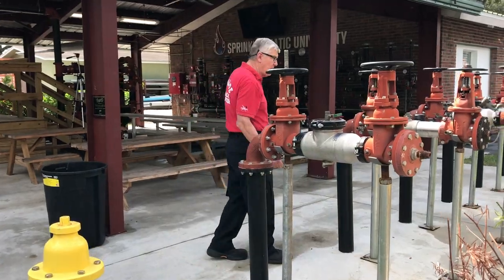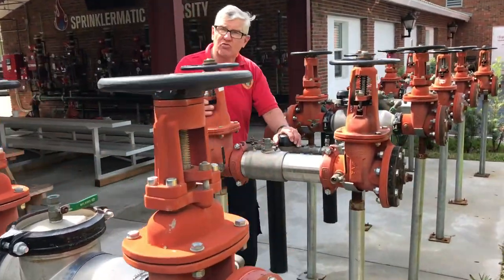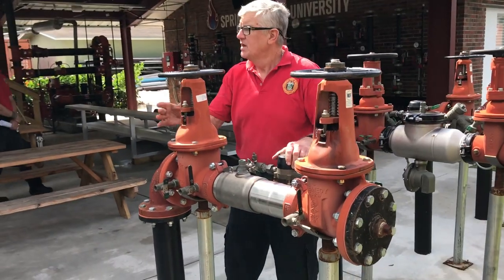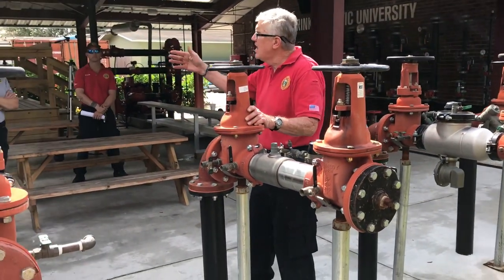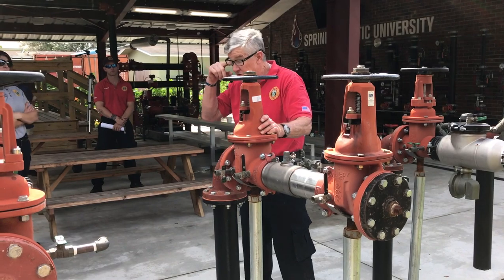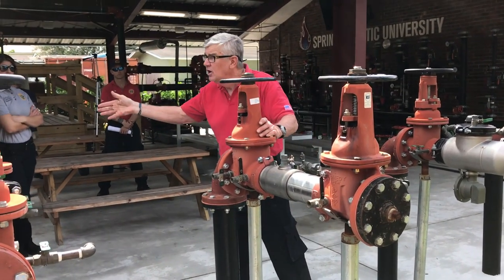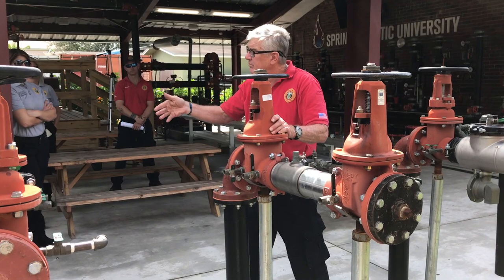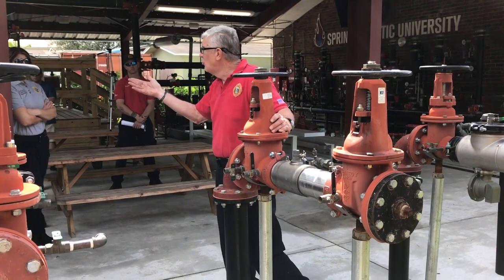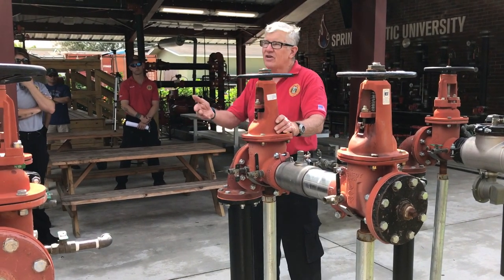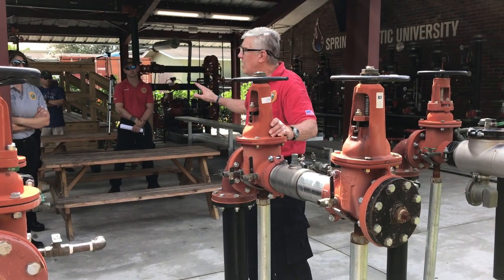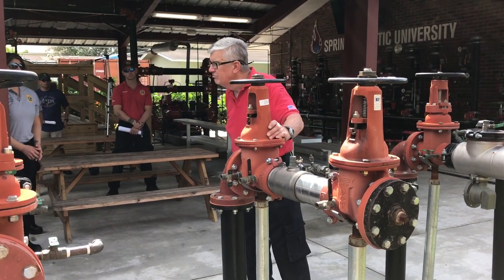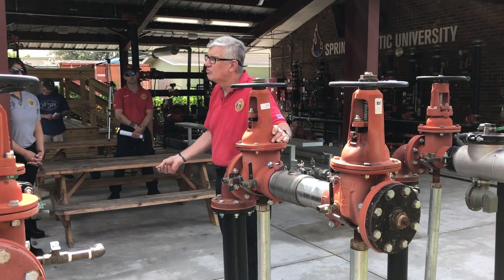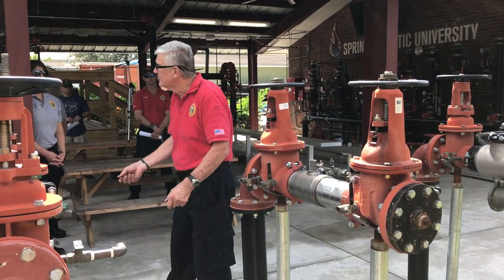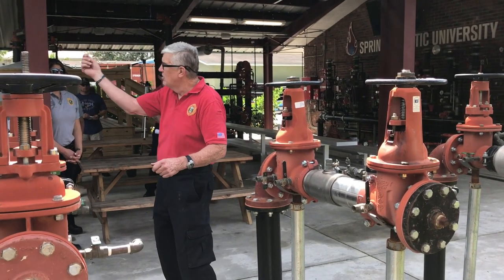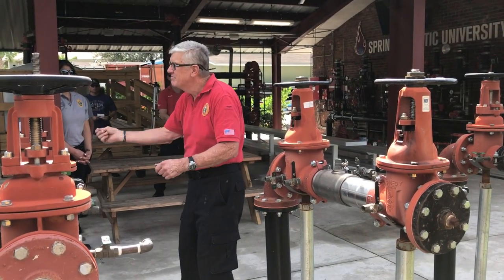If you'll come over here, we have a meter on this one. Why the meter? Because as a building owner, you do not pay for your water for fire protection. You pay for the connections, but not for the actual water. So what may the building owner be inclined to do? Let's say that it's a produce warehouse or a meat warehouse. Connect up a garden hose to a sprinkler system, tap into the sprinkler system, open that up and wash down the porcelain covered walls and ceiling.